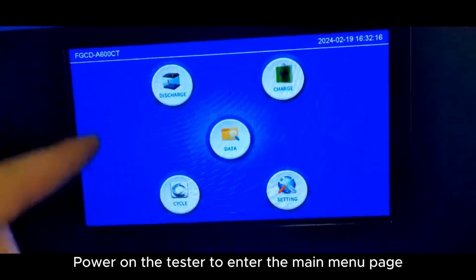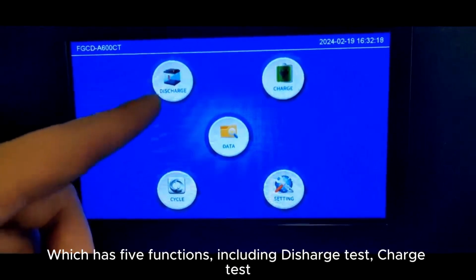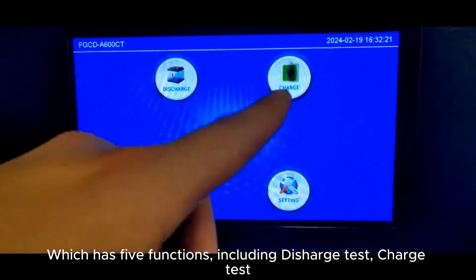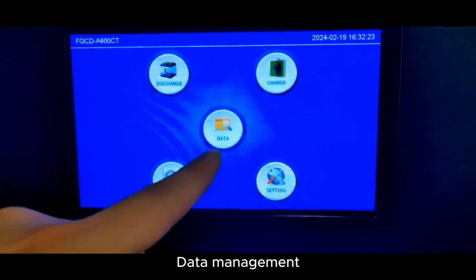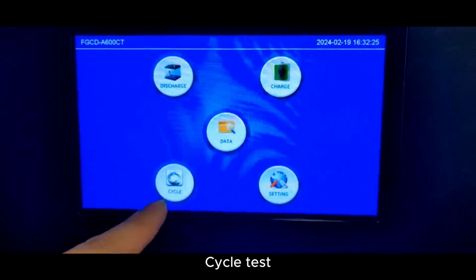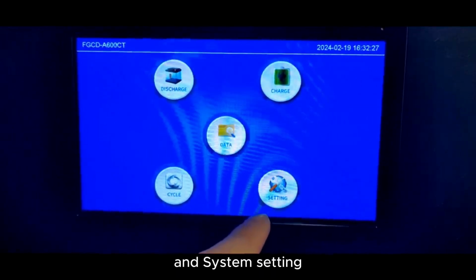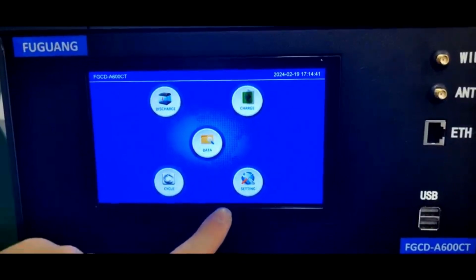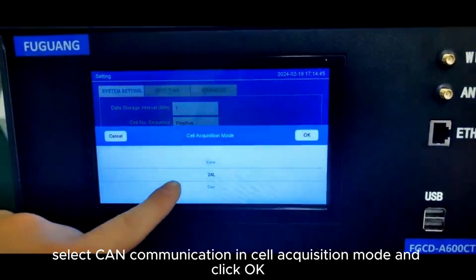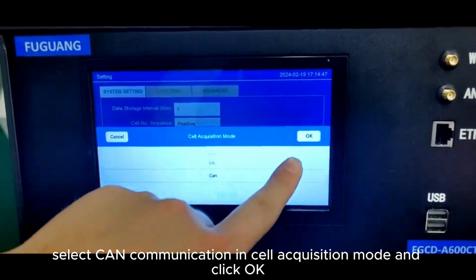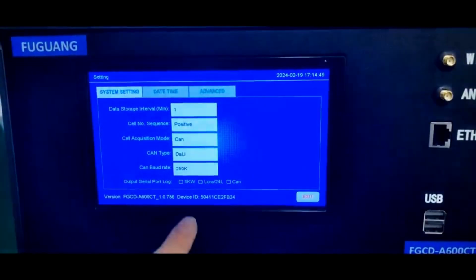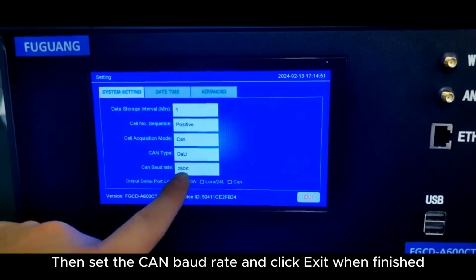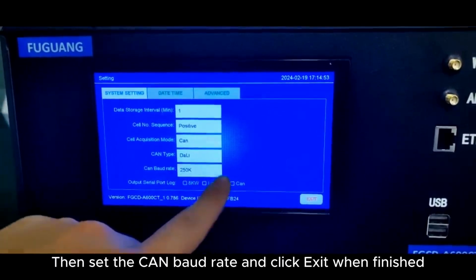Power on the tester to enter the main menu page, which has 5 functions including discharge test, charge test, data management, cycle test, and system setting. First, we click the setting icon. Select CAN communication in cell acquisition mode and click OK. Then set the CAN baud rate and click Exit when finished.